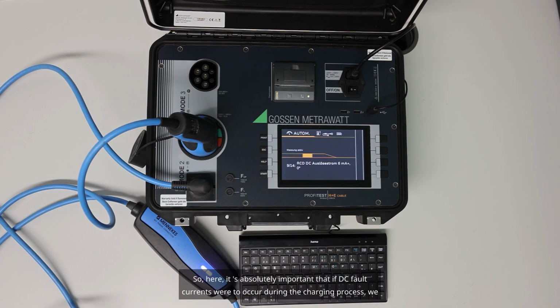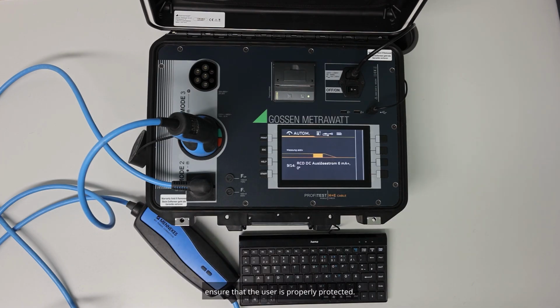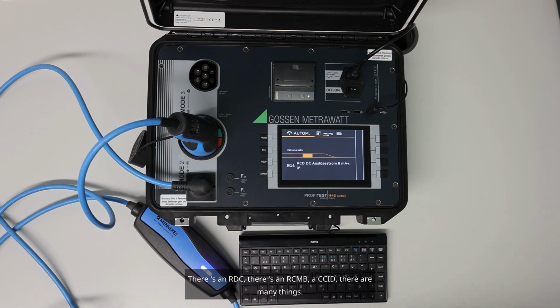So here, it's absolutely important that if DC fault currents were to occur during the charging process, we ensure that the user is properly protected. And that's done by the 6 milliamp sensor system. And we naturally have to test that it also switches off in time. And there are different sensor systems. There's an RDC, there's an RCMB, a CCID, there are many things. Ultimately, it's important that we know what's installed so that we can, of course, include the manufacturer's specifications in the test sequence.